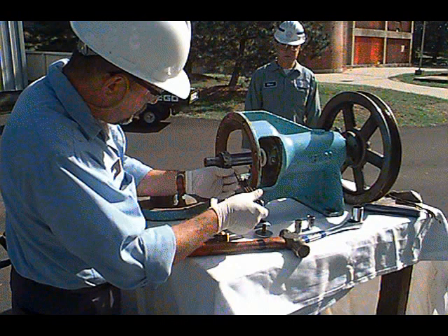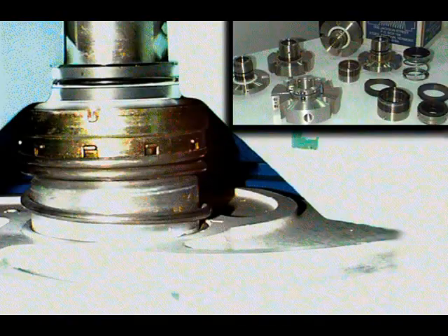For whatever reason, operators are sometimes required to change a mechanical seal. Since there are so many different kinds of mechanical seals, the best guide on how to replace the seal is the manufacturer's literature. However, there are some general points to be made. Mechanical seals are very fragile and can be easily damaged. They should be handled with great care.